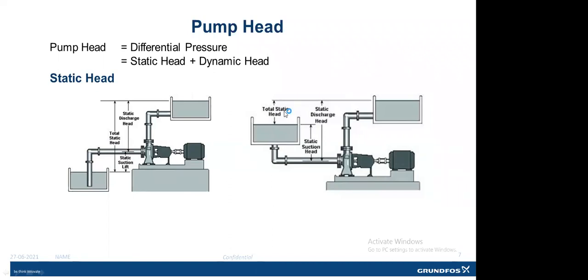So while designing the pump, we need to calculate the static head first and then the dynamic head, and then we can design the pump head. If the system is closed loop, for example an HVAC system with primary and secondary loops, there we can consider the static head as 0.